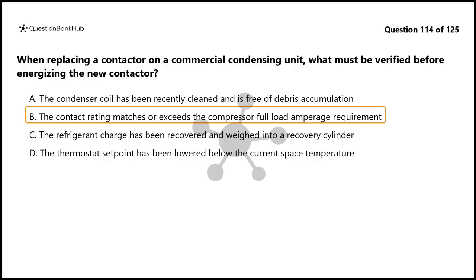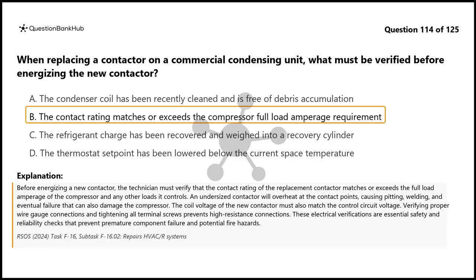The correct answer is B. Before energizing a new contactor, the technician must verify that the contact rating of the replacement contactor matches or exceeds the full load amperage of the compressor and any other loads it controls. An undersized contactor will overheat at the contact points, causing pitting, welding, and eventual failure that can also damage the compressor. The coil voltage of the new contactor must also match the control circuit voltage. Verifying proper wire gauge connections and tightening all terminal screws prevents high-resistance connections. These electrical verifications are essential safety and reliability checks that prevent premature component failure and potential fire hazards.